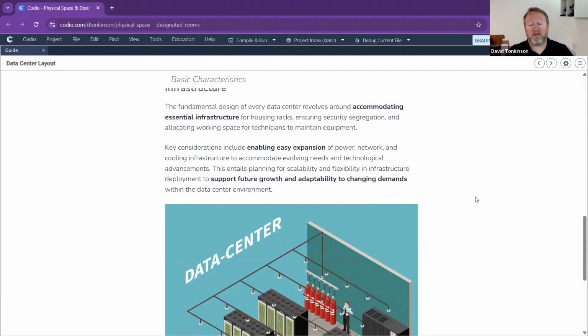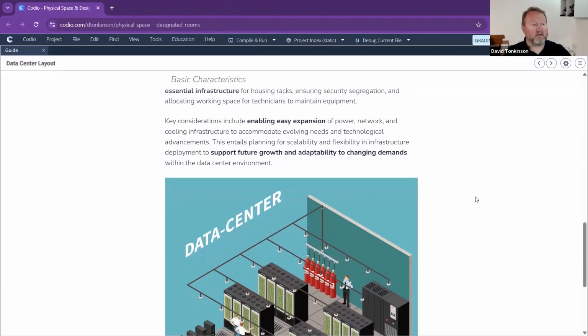You should really consider expansions. Now, a lot of data centers, and some of you do this in yours as well, separate rooms into a particular size. So there is an optimal size for a data center room. And the reason for that is if we only half fill that room with equipment, we are still pumping in air conditioning to keep that cool. So if we have a smaller room and we fill it to the top, that then becomes an efficient room. So if we have multiple small rooms, yes, we can then control it and make it more and more efficient because we can shut off the rooms that do not have any equipment in.